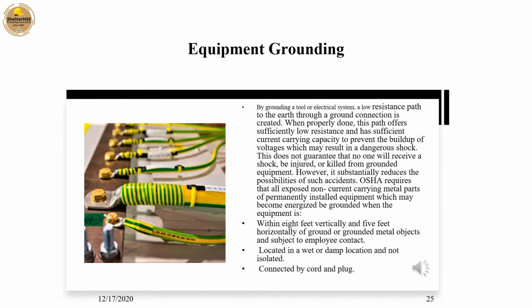By grounding a tool or electrical system, a low-resistance path to the earth through a ground connection is created. When properly done, this path offers sufficiently low resistance and has sufficient current carrying capacity to prevent the buildup of voltages which may result in a dangerous shock. This does not guarantee that no one will receive a shock, be injured, or killed from grounded equipment. However, it substantially reduces the possibilities of such accidents.